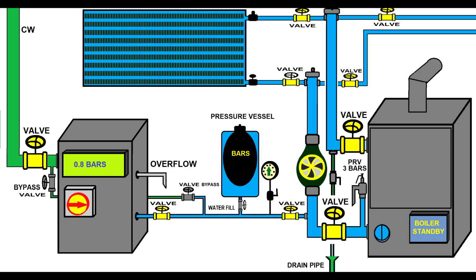You might have some pockets of air in the installation. Check for leaks. Check the air eliminators. Check the pressurization unit. Check the pumps. Check the pressure vessel. By the way, I forgot to tell you, the pressure vessel should be pressurized to the right pressure. So check everything, and when you are satisfied, then you can enable the boiler.